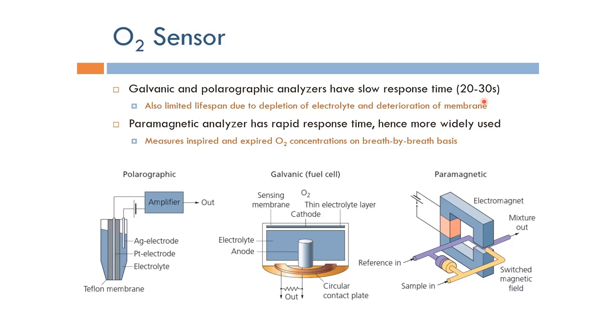The third technique is the paramagnetic technique, which relies on the fact that oxygen has paramagnetic characteristics, meaning it's affected by a magnetic field. Whenever we apply a magnetic field, the oxygen follows the magnetic field. In steady state without a magnetic field, oxygen molecules can be arranged in any random orientation. Whenever we turn on the magnet, the oxygen will have to align with the magnet.